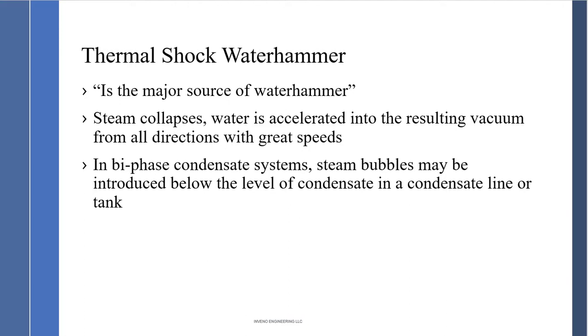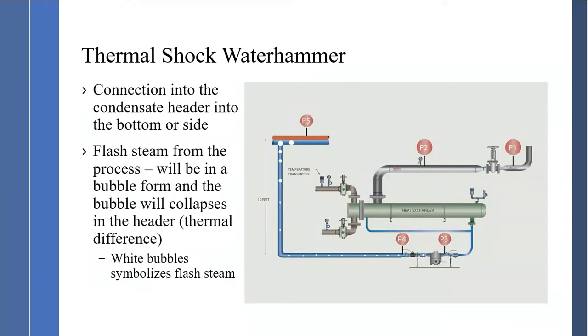With thermal shock, steam collapses and water is accelerated into the resulting vacuum from all directions with great speed. In a bi-phase condensate system, steam bubbles may be introduced below the level of condensate in the condensate line, tank, or condensate tank, as shown on the right-hand side.